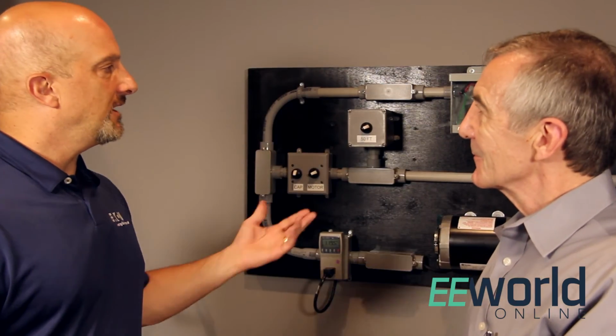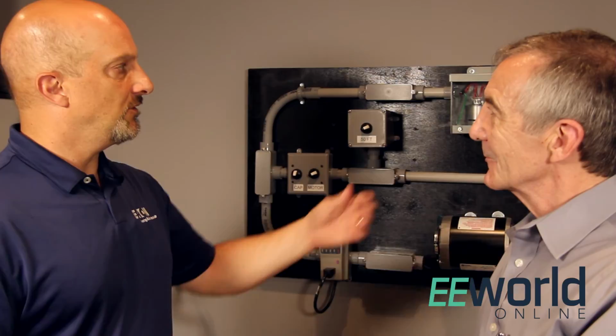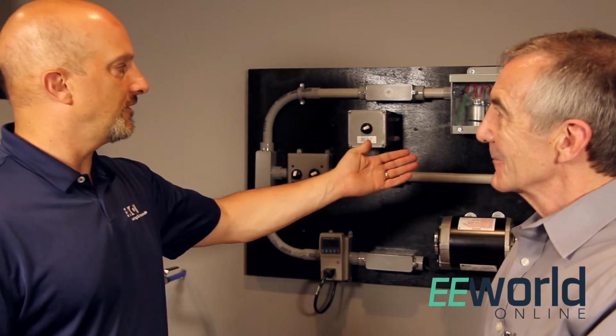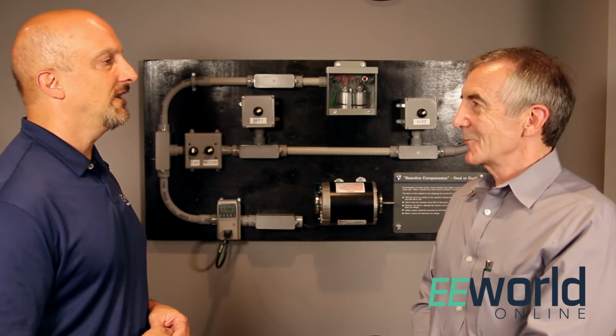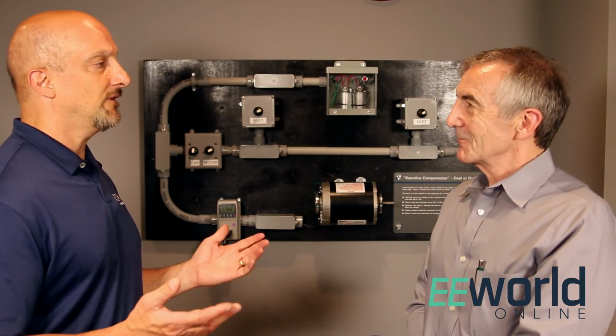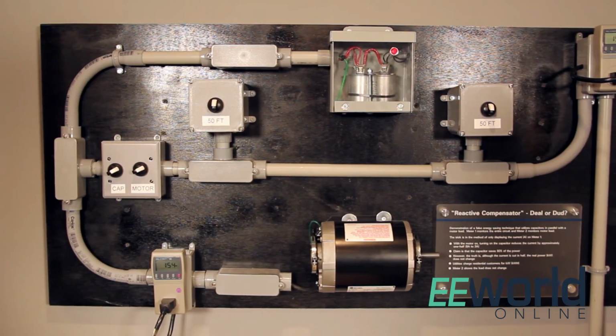So here they might exaggerate that, and they might say that there's 10% losses in this wire, but of course with 18 gauge wire on a small motor like this with 5 or 6 amps running, it's not comparable to what you'd see on a real system. So again, typical losses on a line like that might be 1 to 2%. So if you can only save what you lose, you can only save 1 or 2%. Their claims are typically like 8 to 25% of your power, which again is impossible.